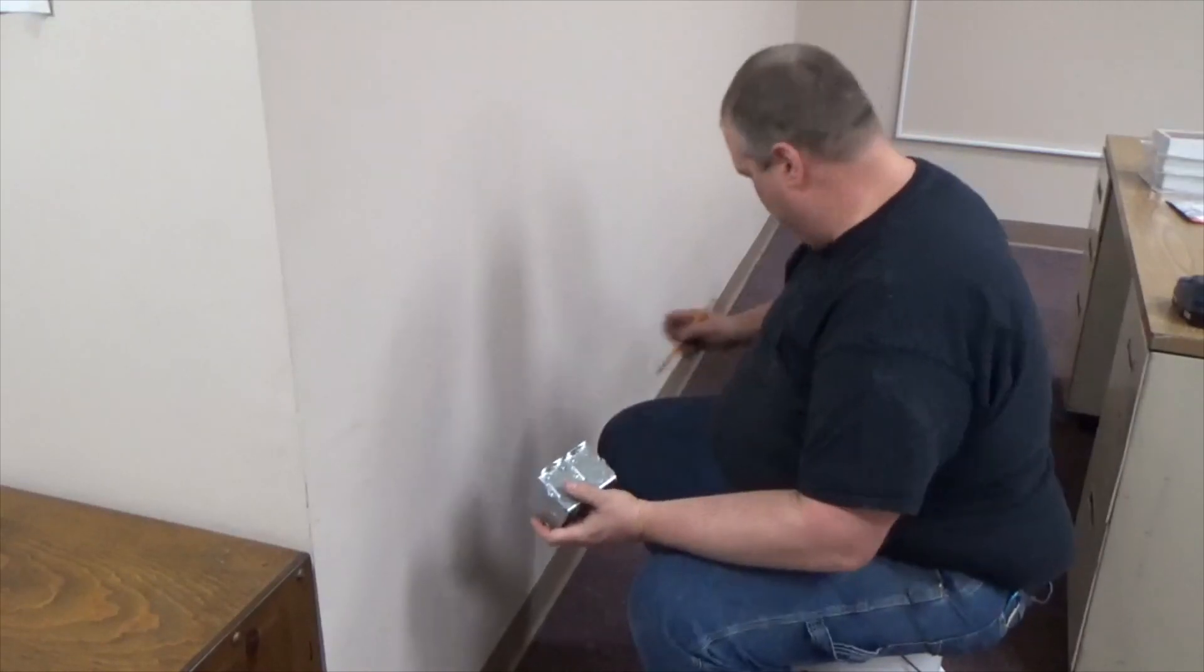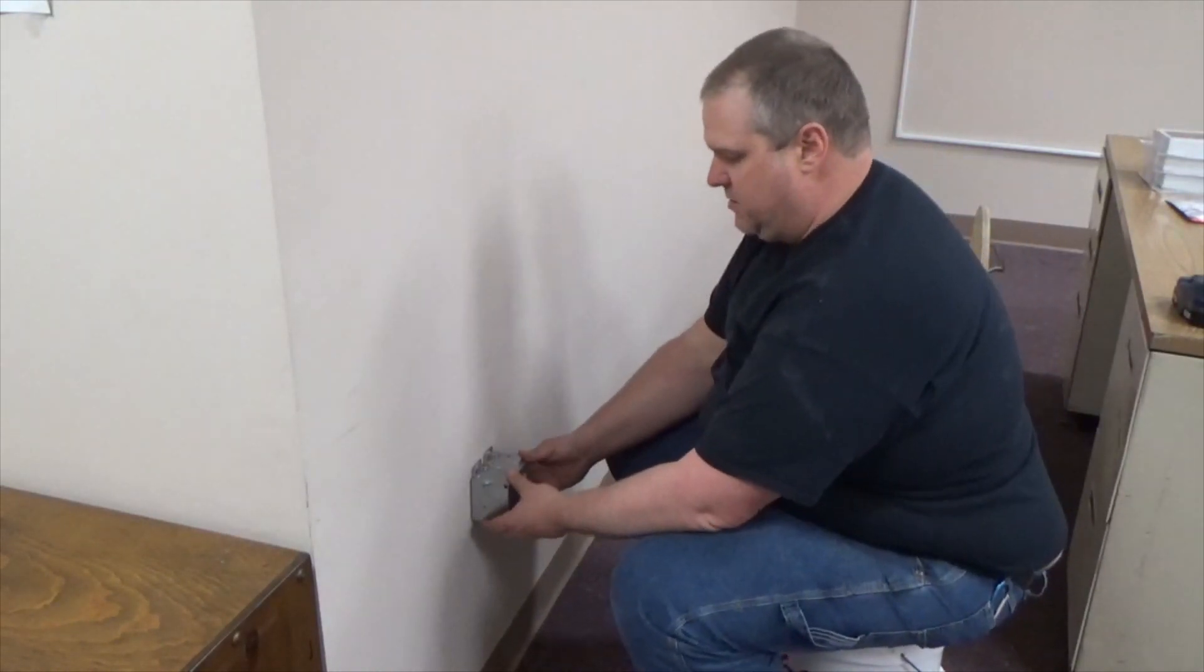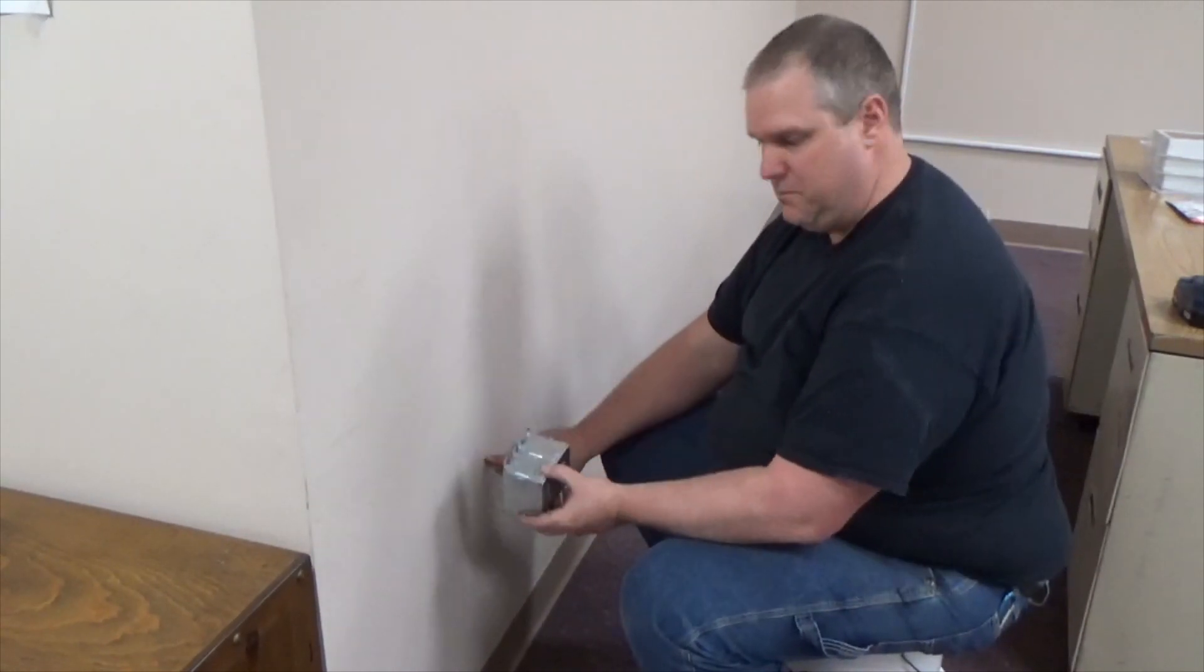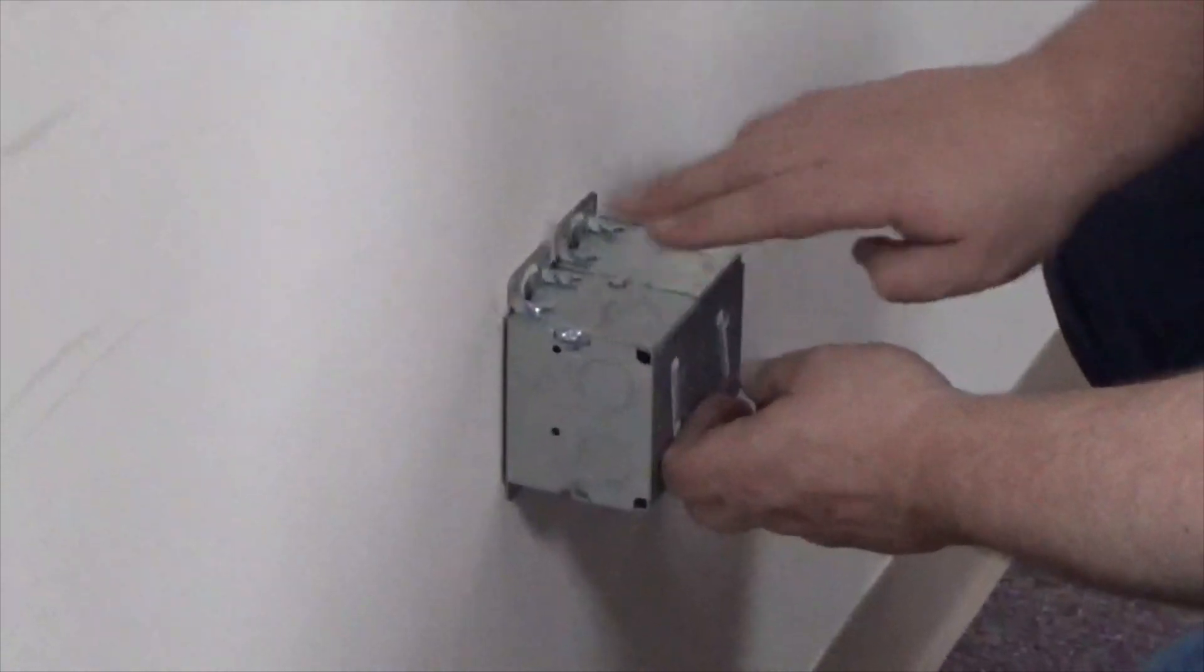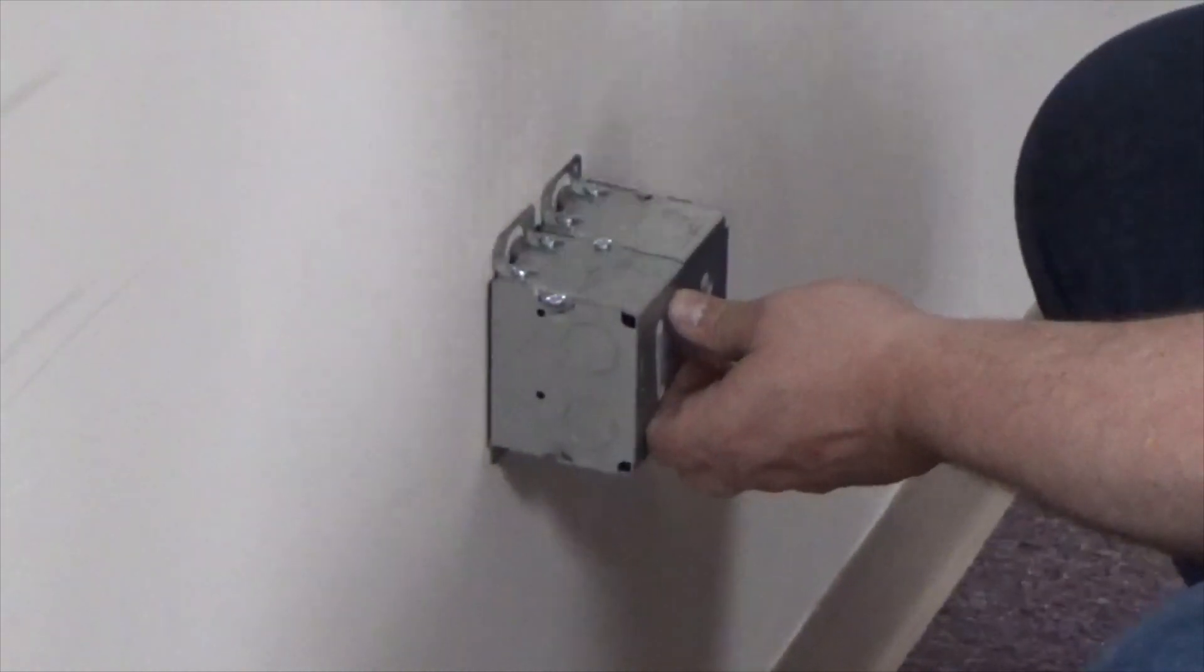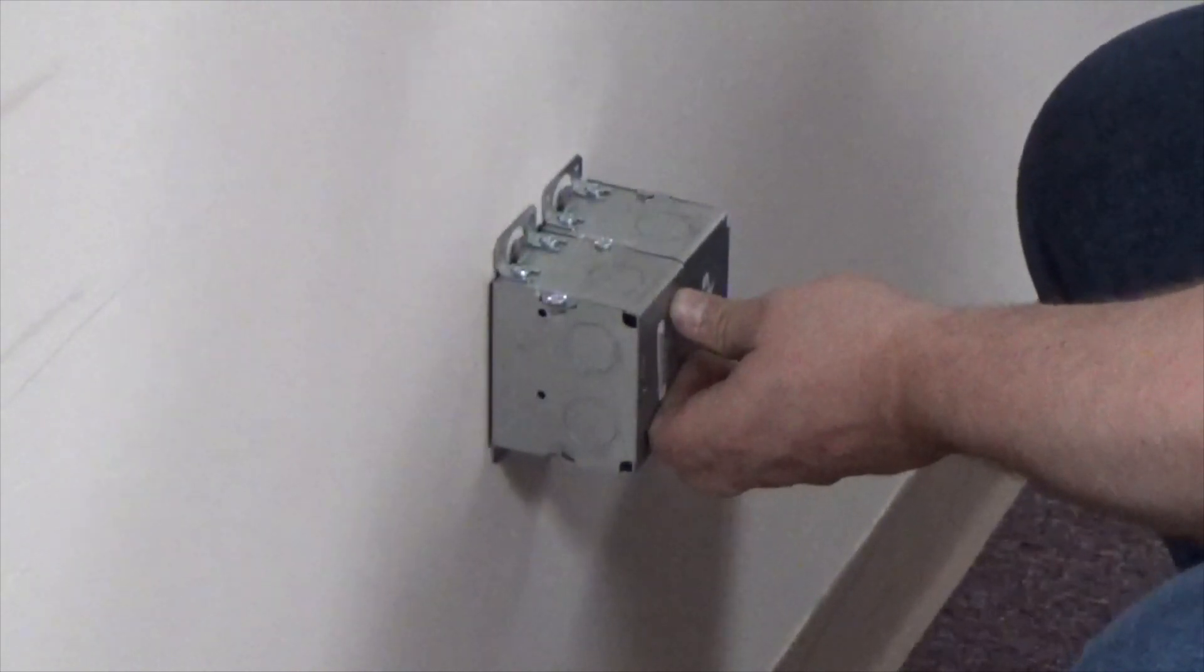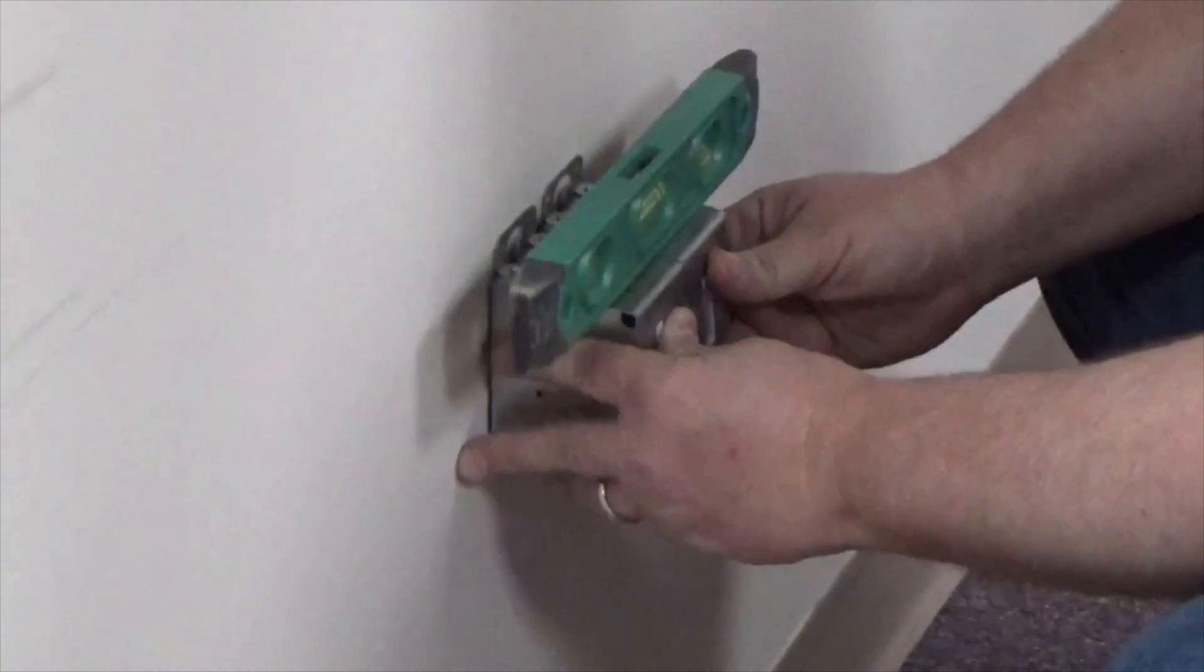So again, I've got my jab saw. My jab saw is what I'm going to need in order to cut the sheetrock, in order to put the box in the wall. So let's get started. So now what we're going to do is we're going to take this and we're going to put it up against the wall. So I want the top of this box to be at 20 inches above finished floor. I'm going to take my level and I'm going to put my level on the box and I'm going to level it up.